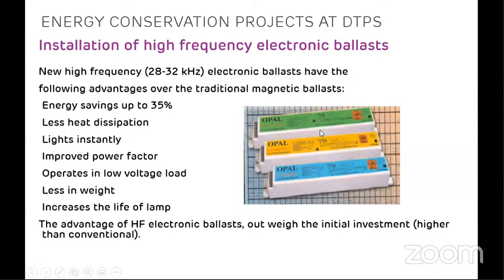See, power factor is reduced because of the coil. So as we eliminate the coil and install an electronic driver circuit, the power factor is improved. In the case of old chokes, you may have seen that whenever the voltage is lower, the light intensity reduces drastically. However, these transistors control the lights in such a way that even with slightly lower voltages it gives similar light output. The weight of the fitting is reduced and the life of the lamp is increased.